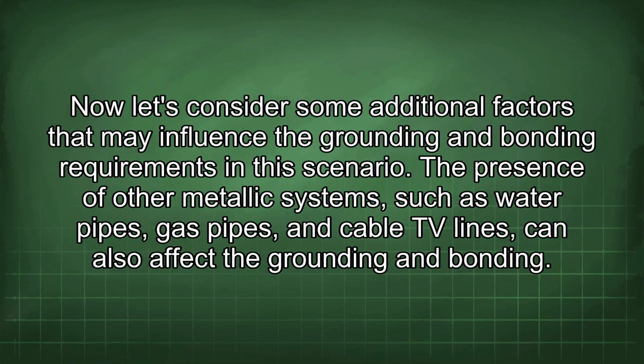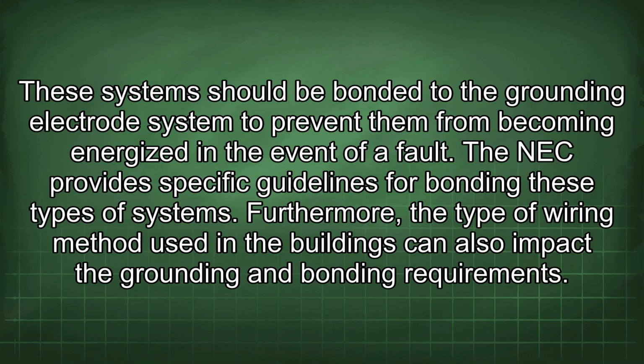Now let's consider some additional factors that may influence the grounding and bonding requirements in this scenario. The presence of other metallic systems, such as water pipes, gas pipes, and cable TV lines, can also affect the grounding and bonding. These systems should be bonded to the grounding electrode system to prevent them from becoming energized in the event of a fault. The NEC provides specific guidelines for bonding these types of systems.